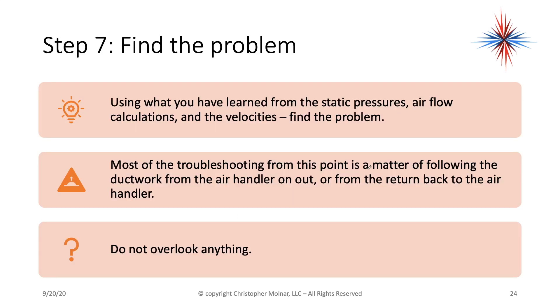Finding the problem is your final step. Using what you've learned from the static pressures, the airflow calculations, and the velocities, find the problem. Most of the troubleshooting from this point is a matter of following the duct work from the air handler outward for the supply side, or from the return back to the air handler. Don't overlook anything — don't skip portions of duct work, because you're liable to find a leak.